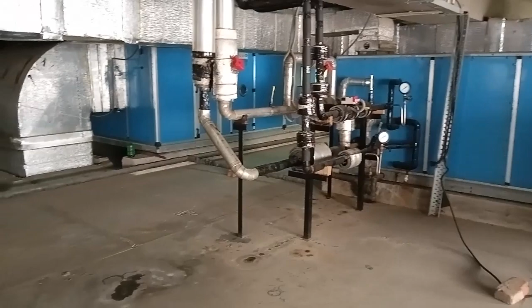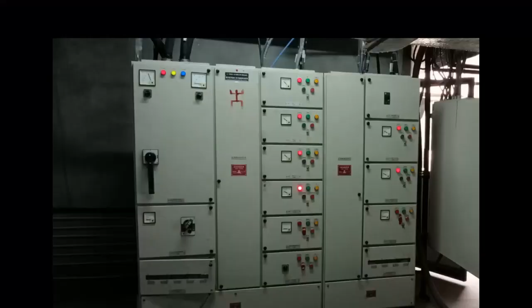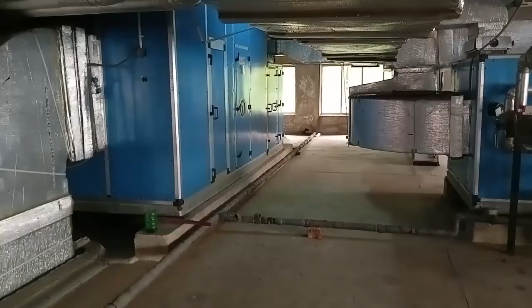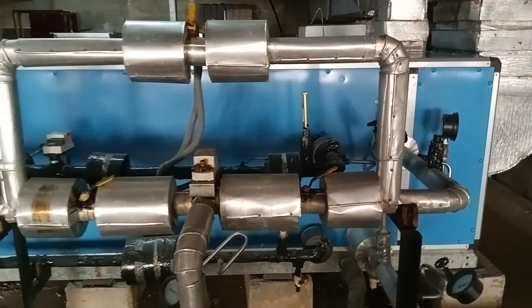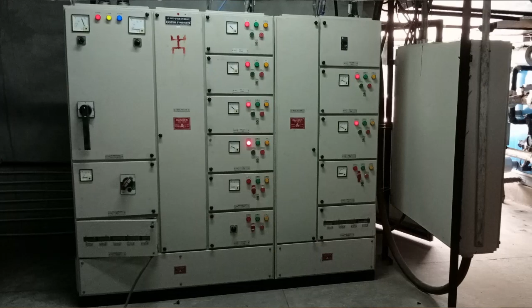Clean room, as we mentioned, is a special assembly, a closed room, and we need to wash the clean room by clean air only. So we need to generate the clean air for running the clean room, and it works on the principle of 24 hours, 365 days at a stretch. We are standing at the heart of the clean room. Around 30% of the air is coming from the atmosphere, and 70% of the air of this system is coming as return from the clean room that we have already seen at the ground floor. The mixing of these two airs comes at the input of this chamber.